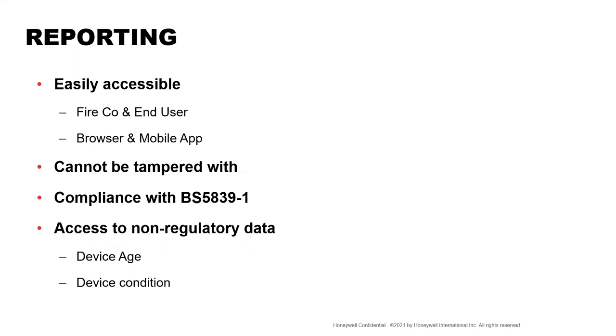So the information that will be given to him will be available to the end user and the service and maintenance company. It will be the device installation date, the recommended life expectancy of that device. Some devices have a longer expected life expectancy than others. CO detection, for example, only has a life expectancy of 6 years because of the cell that detects CO. A normal standard smoke detector that we've probably all got in our houses or in the offices in which we work, will be 10 years.